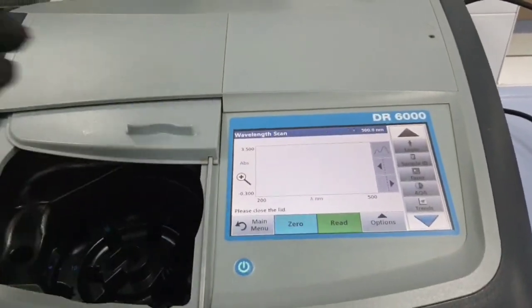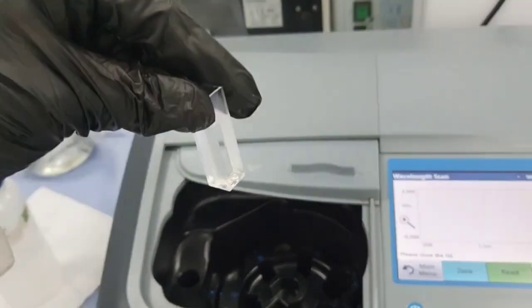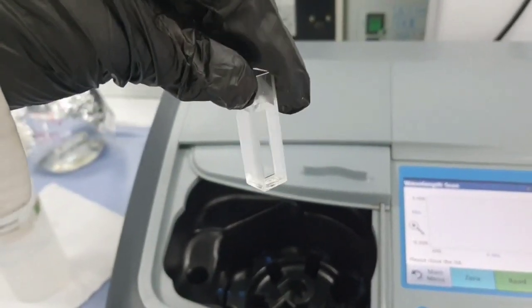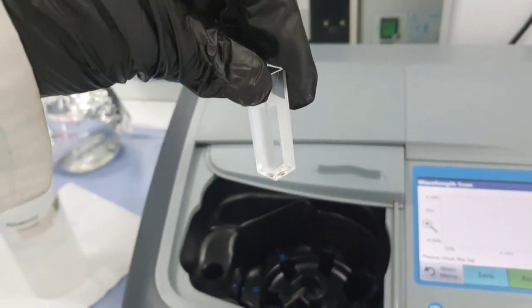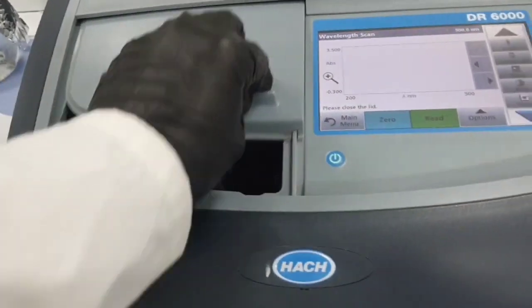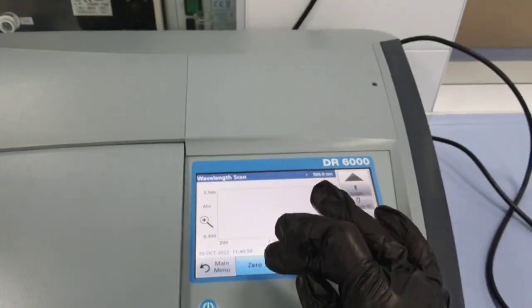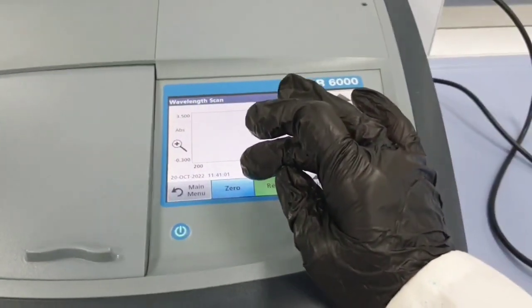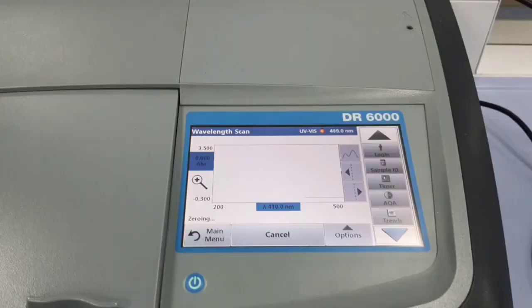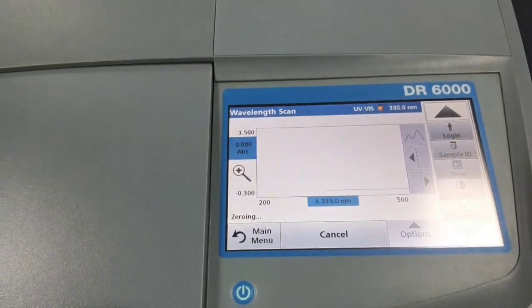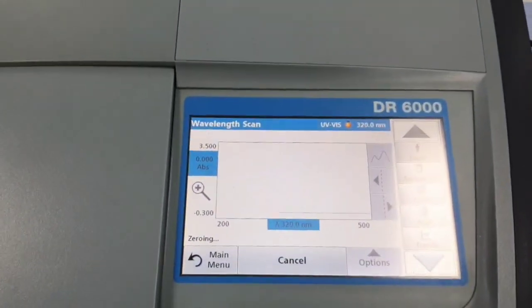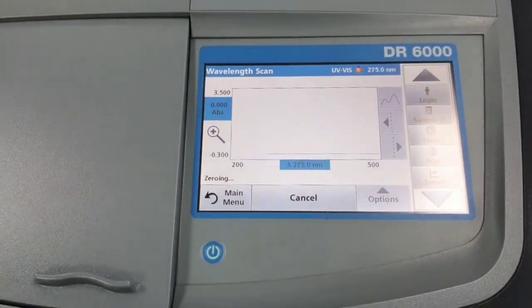I have to put my cuvette here and also make sure there are no impurities at the edges or on the surface. This arrow should be pointed here. I'll put it in, and first of all I have to zero it, and there should be nothing. This is deionized water, so I will say zero. Now you can see a straight line coming up. Since this is distilled water, there would be no peaks.